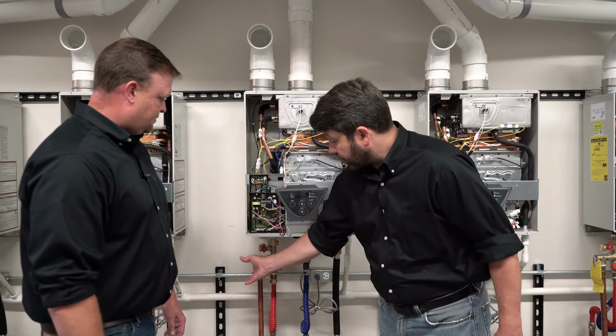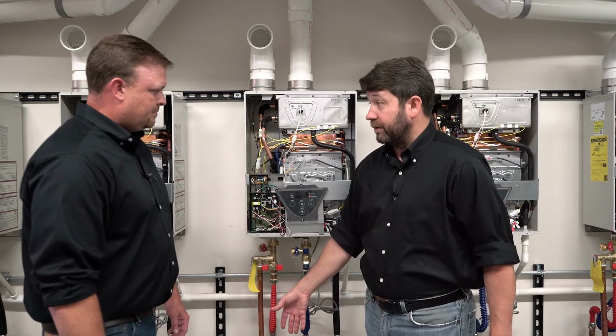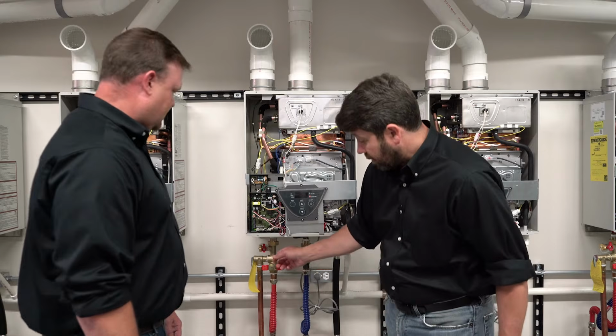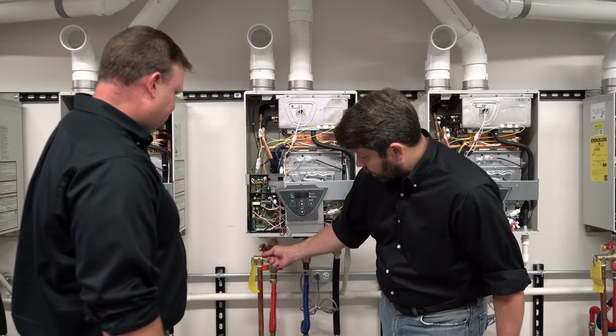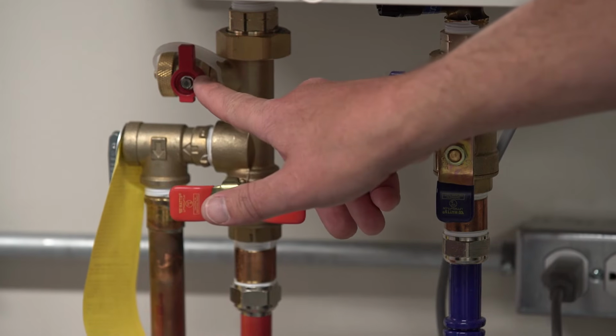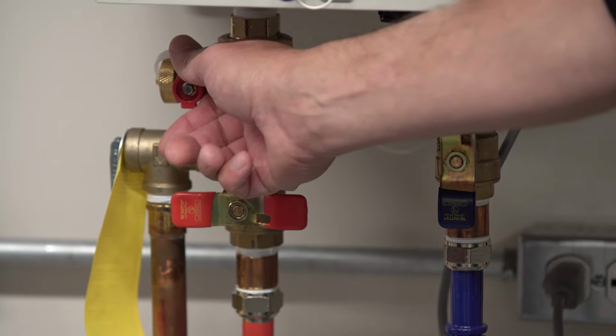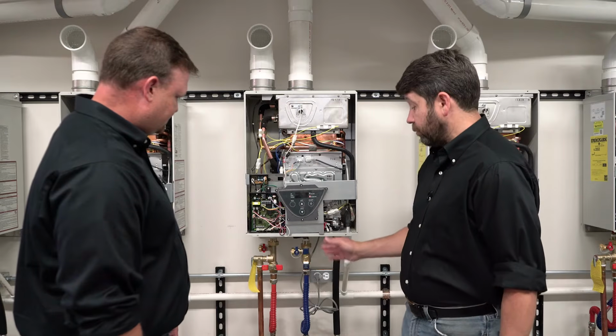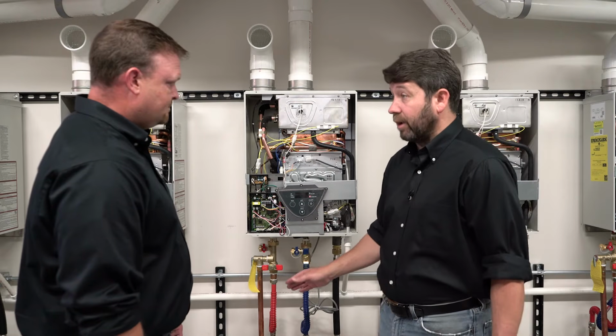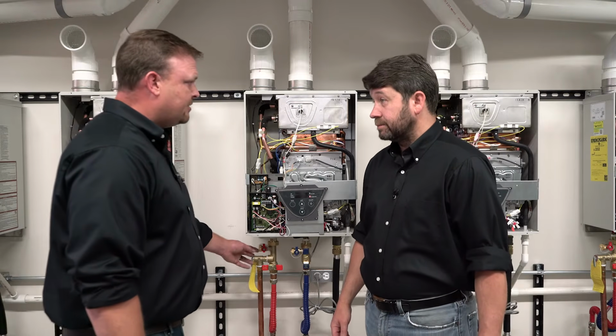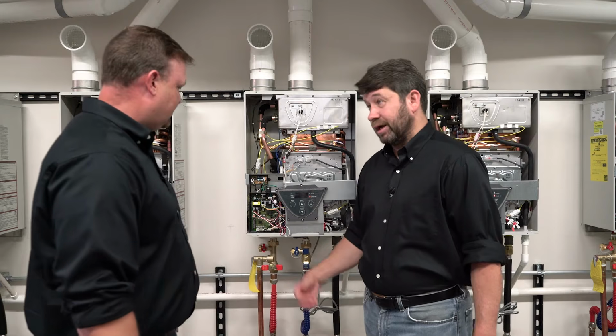And so if we open up the pressure relief valve, if it's safe to put that somewhere where it's not going to harm anything by leaking, if we don't want to do that, then we can hook up a hose to our service port, and then we can open this valve. And that's going to allow water to flow through the heater, and we know then that it's coming and it's flowing the right way. Okay, and if you don't have water coming out, then you've got your connections backwards.